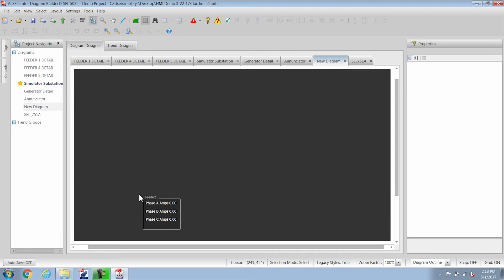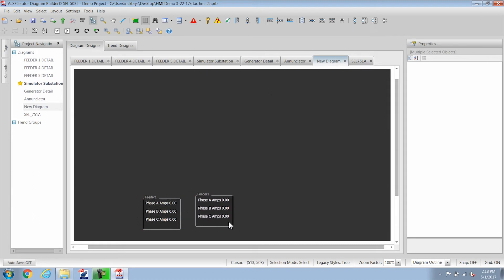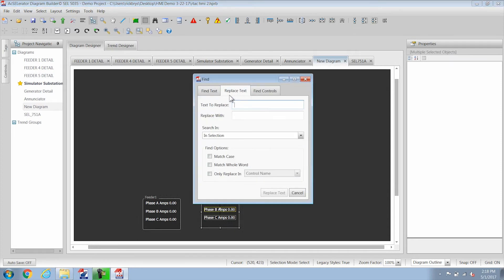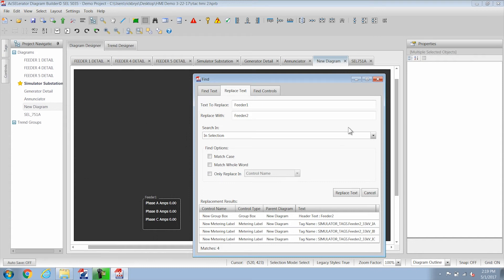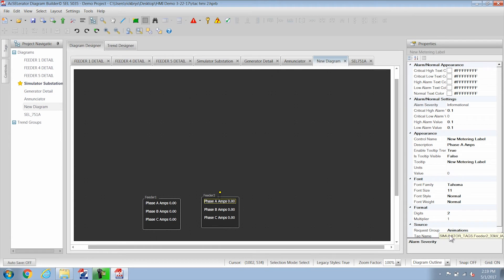Now all of these are for feeder 1 so what I can do is highlight all of this. Control C to copy, Control V like Victor to paste. Now I have two that are identical. While it's still highlighted I can do Control F for find and type in feeder 1 and then replace text with feeder 2. Click on replace text and you can selectively replace different things. I'm replacing everything in the selection. And you can see here that the group box name has changed to feeder 2 and all of the tag names have also changed to feeder 2.